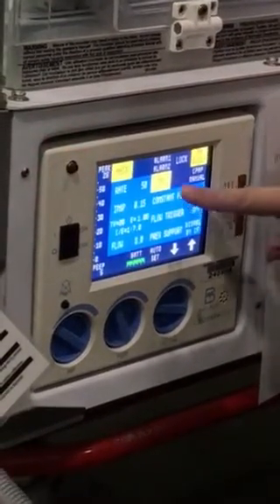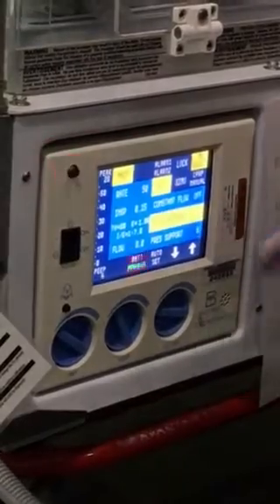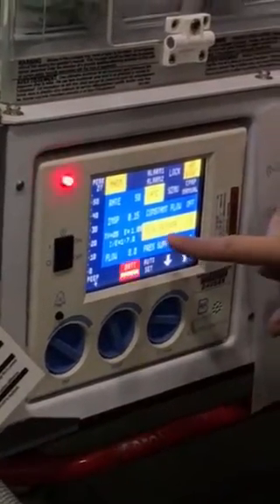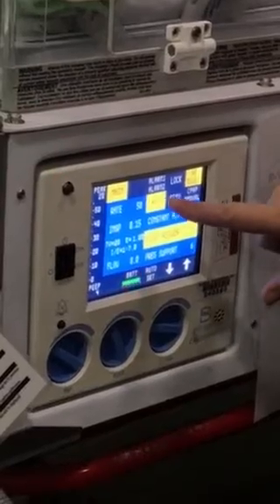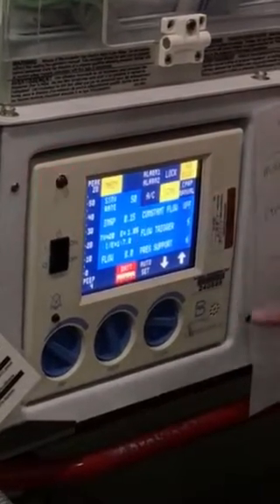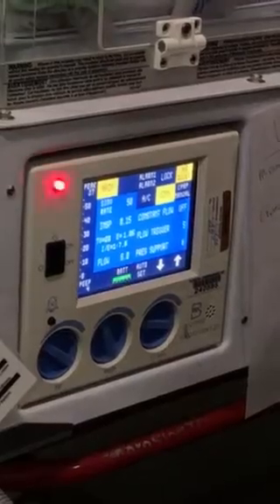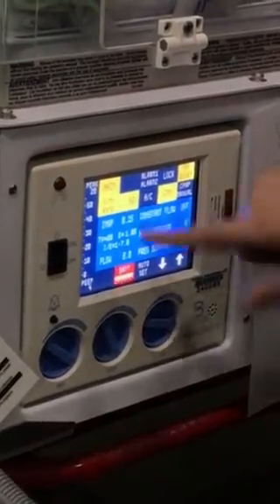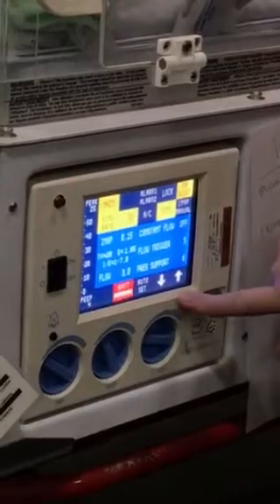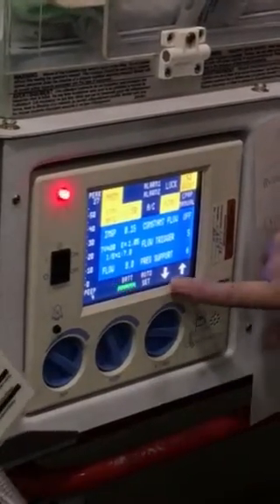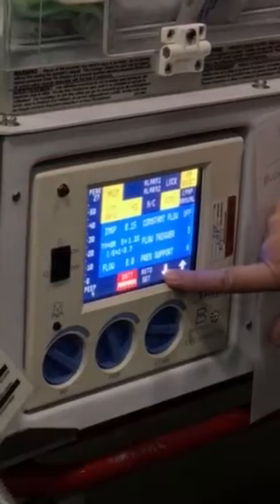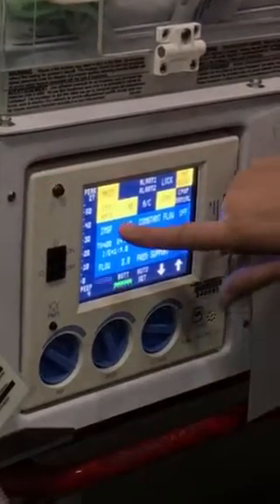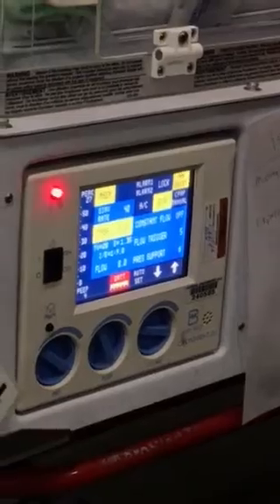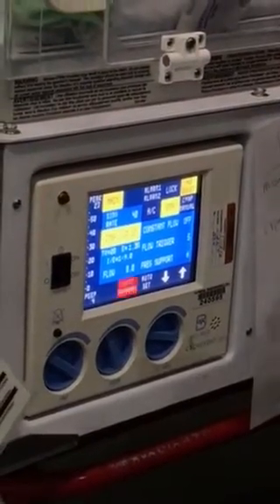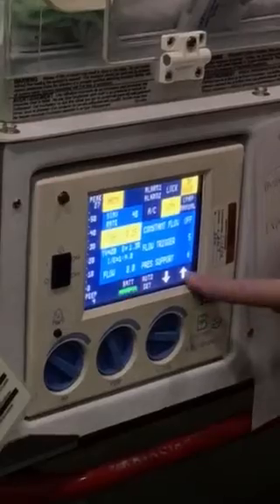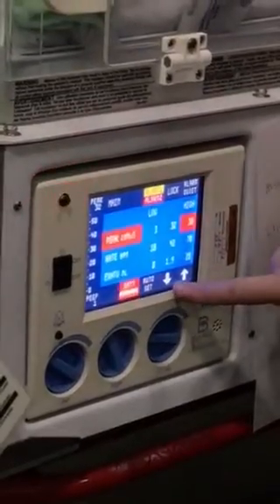So we're going to turn the, hold on, flow trigger, that's it. I knew one of them worked. So when you hit the flow trigger on, then you can go assist control or SIMV. Okay, so we'll go over to SIMV. All right, so then we can dial in our rate. These we're just going to touch, and we have our up and down arrows here. Okay, so say we have a term baby, and we need really just a rate of 40. Your inspiratory time, you're going to talk to your practitioner about that. We often use 0.3, 0.35, or 0.4. So this is a little bit low here. So we'll set that.